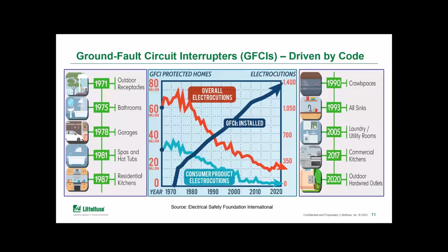For the majority of its existence, the GFCI, whether we're talking receptacles, circuit breakers, or an inline cord device, was limited to 125 volt single phase circuits, 20 amps and below. But a more significant change occurred in 2017 that I want to highlight. In that code cycle, NEC 210.8(B), the section for GFCIs for other than dwelling units, raised the levels where GFCIs were required up to single phase 50 amps and three phase 100 amps.